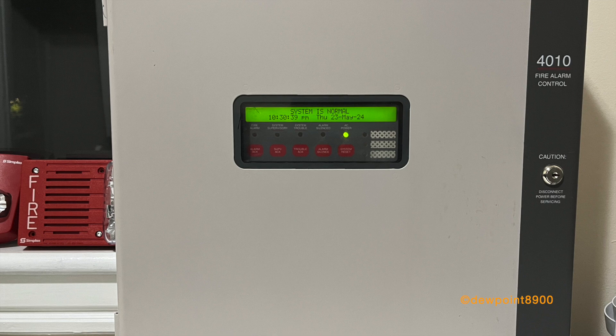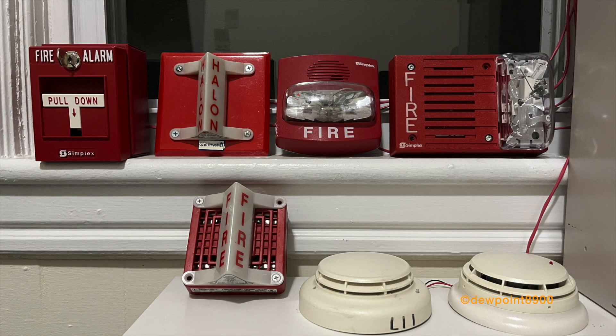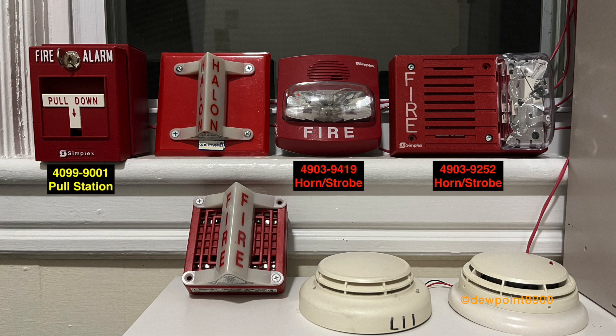So let's jump right into this. For this demonstration, the 4010 is configured for both general fire alarm and agent release. On the fire alarm side, we have a 4099-9001 pull station, and the signals include a 4903-9419 horn strobe and a 4903-9252 horn strobe. Both strobes are set to smart sync, and the horns will sound in temporal coding.